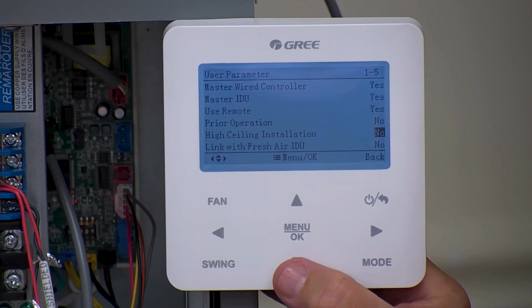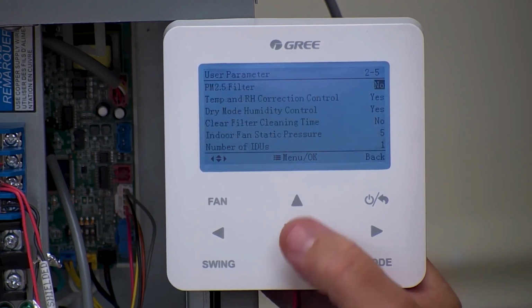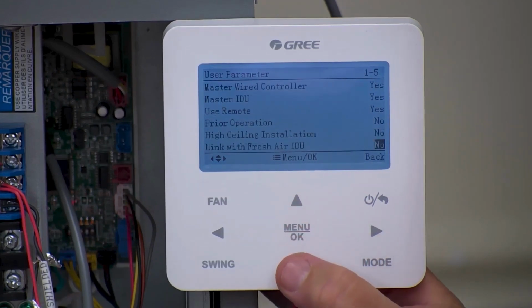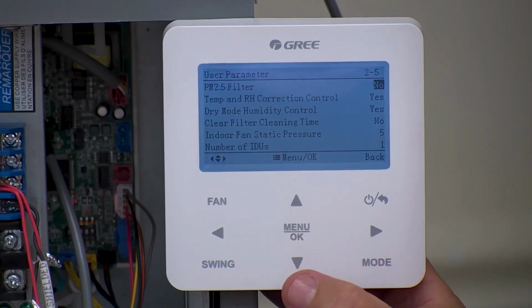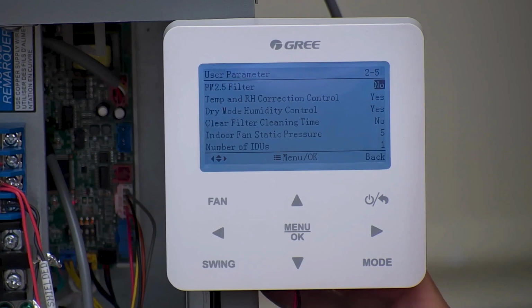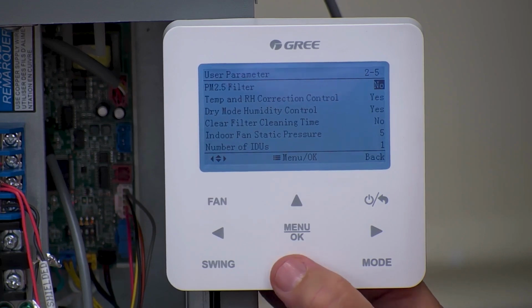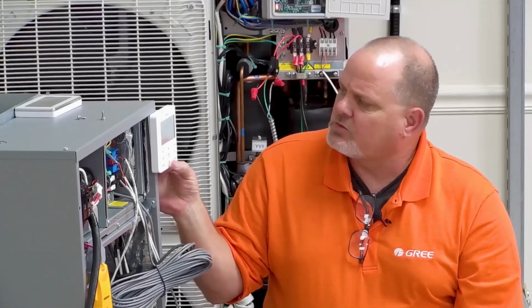Prior operation. I wouldn't worry about that so much. High ceiling installation is not really going to apply to an air handler. Link to fresh air, that's only for a fresh air kit. So a lot of this menu stuff that I'm telling you here, I can tell you we've already changed the whole menu structure because we've changed it so that you're only getting to the ones that really mean something to you, to us in the States. There's a lot of options in these controllers and we don't necessarily use them all.